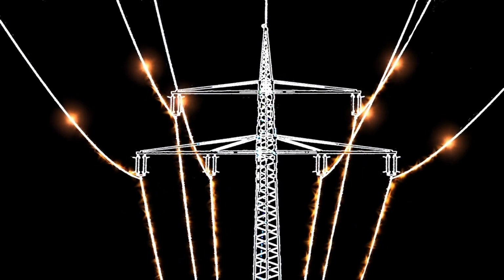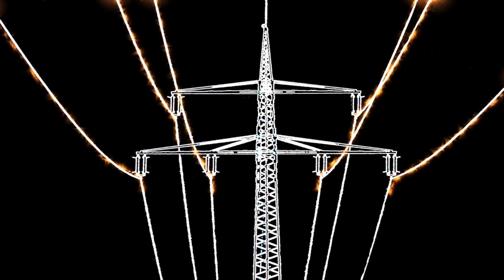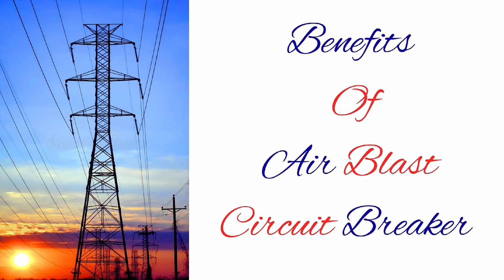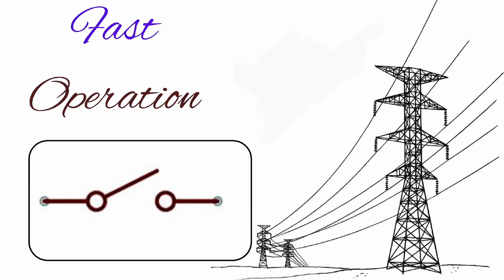As we have known the limitations of air blast circuit breakers, why are we interested in it? Air blast circuit breakers, ABCBs, offer several advantages that make them an ideal choice for high-voltage transmission systems. Some of the key benefits of air blast circuit breakers include the following. 1. Fast operation. Air blast circuit breakers are designed to interrupt faults quickly, reducing the risk of damage to electrical equipment. Their fast operation ensures that faults are cleared before they can cause significant damage to the system. This is particularly important in high-voltage transmission systems, where faults can have far-reaching consequences.